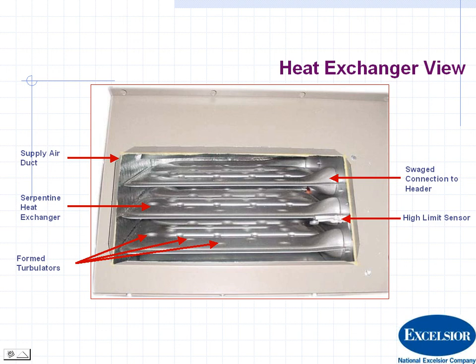Here is the picture of the heat exchanger. It is a clamshell, and it is a serpentine heat exchanger, and aluminized steel. But I was talking about the condensate drain. It is right down here, right where the tube or the clamshell is swedged or swaged to the header assembly. There's a drain line right there, and in the summertime, this inside heat exchanger is open to the hot, humid outside air, and if you're blowing cooling air over it, sometimes the water condenses in the heat exchanger. But that little drain right there prevents any water from collecting and corroding in there. So the heat exchanger has a very long life.